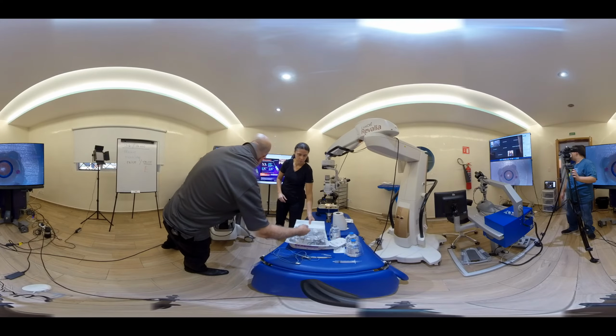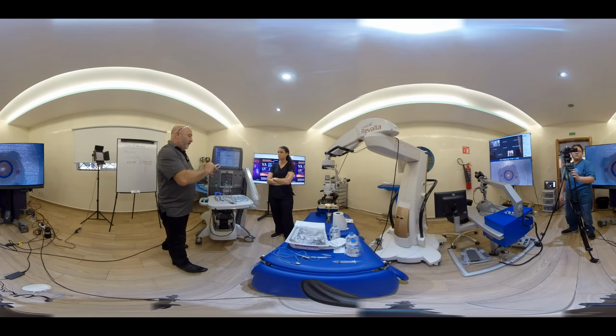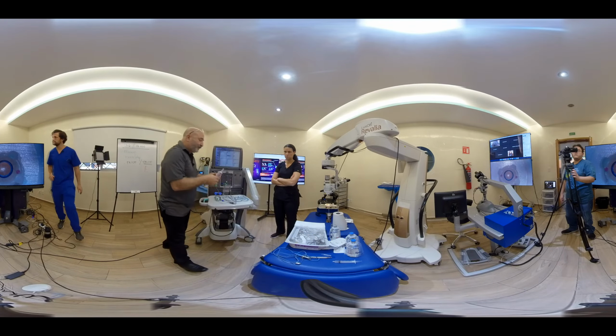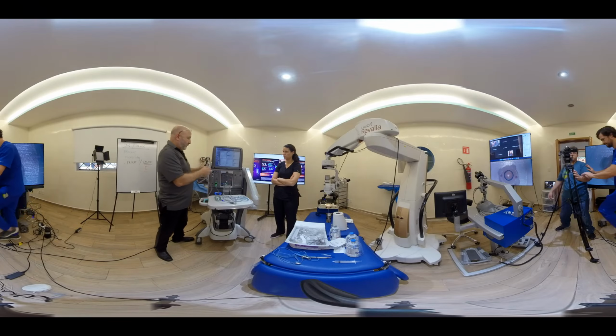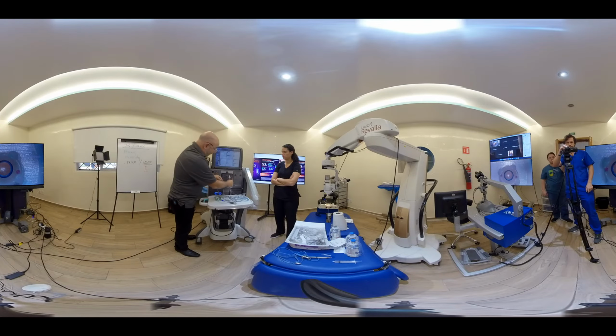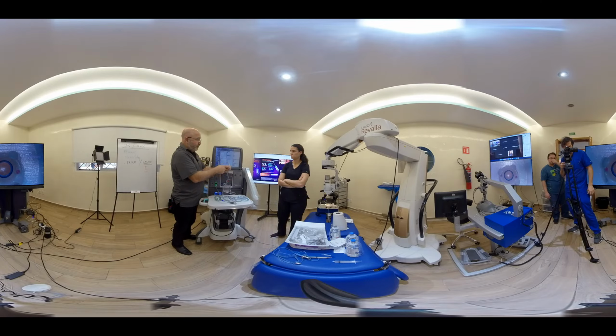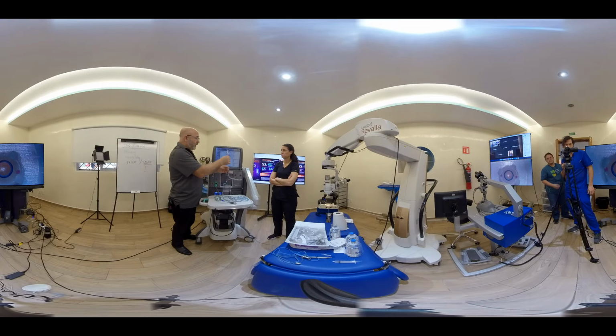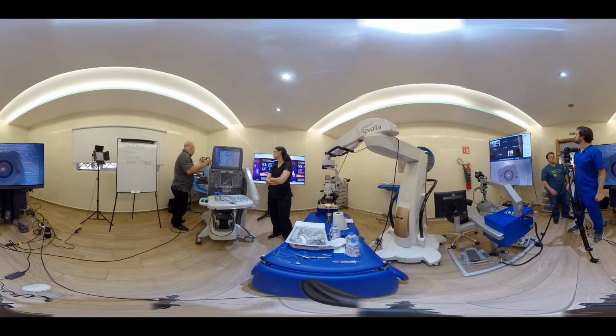What else do we do? One of these. So here comes the giving set line for the bottle. So we have our red line here that takes the fluid from the bottle and puts it into the cassette that feeds the 2 infusion chambers. And this grey one is pressurization. So this sends pressurized air into the bottle so that the fluid will fall into the line when we ask for it. So let me get a bottle.